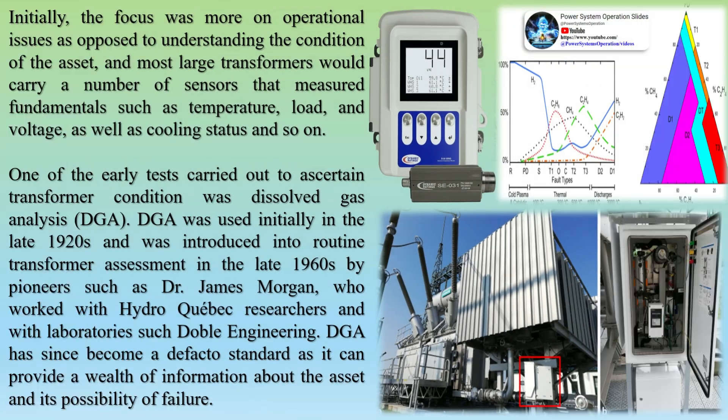Transformer Dissolved Gas Analysis (DGA) is a technology used to monitor the health of transformers. It works by analyzing the gases dissolved in the transformer oil, which can indicate various types of abnormal events occurring within the transformer. There are two types of DGA monitoring: key gas monitoring and multi-gas monitoring.